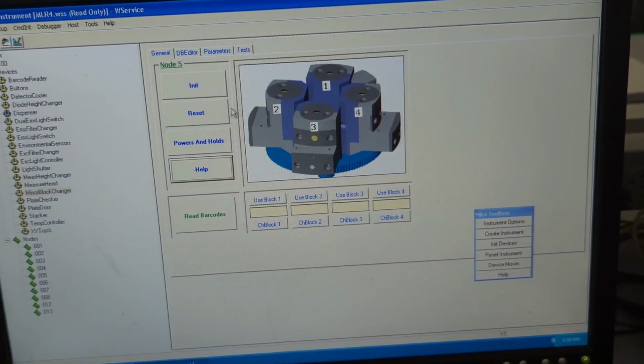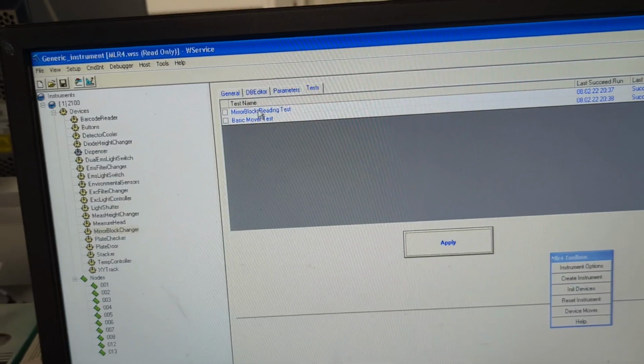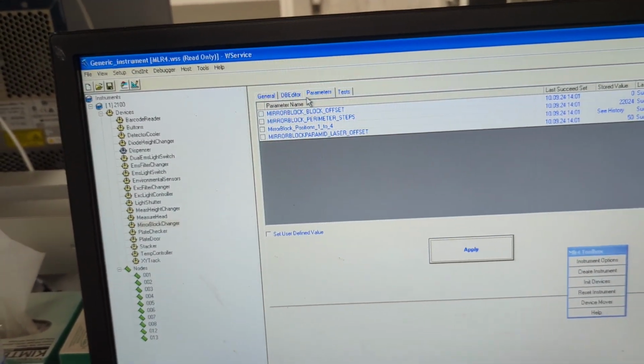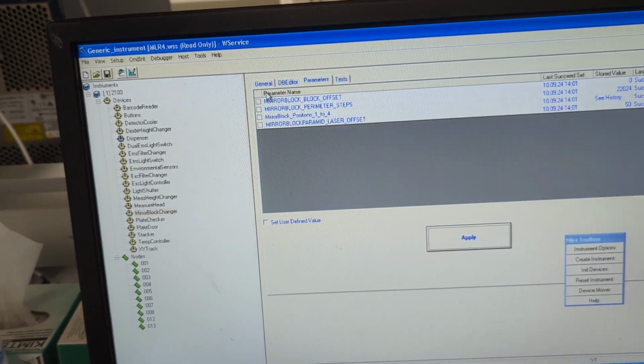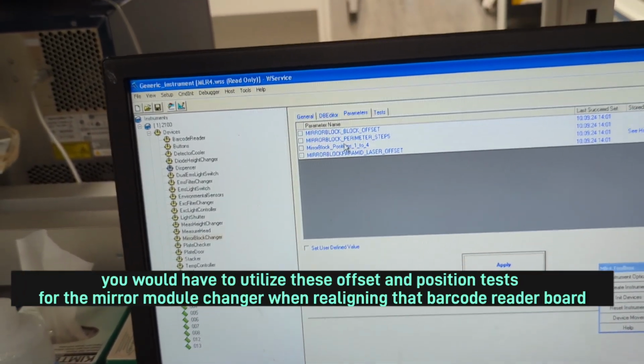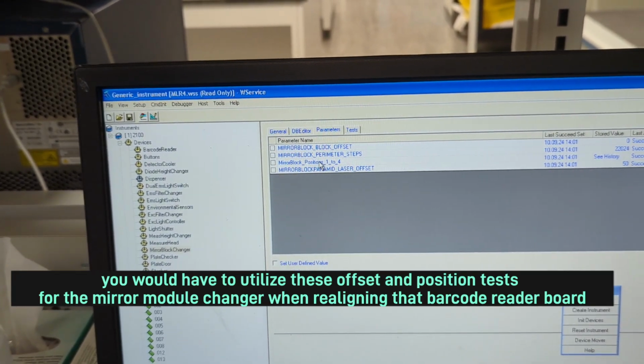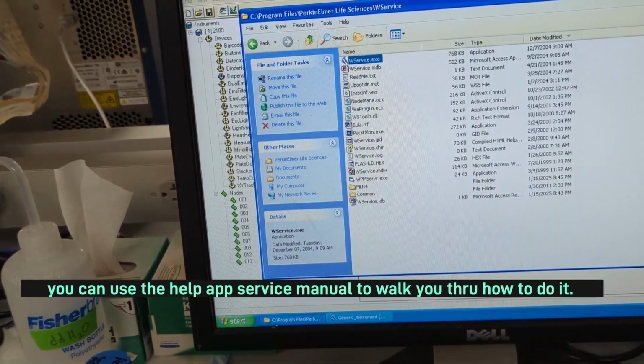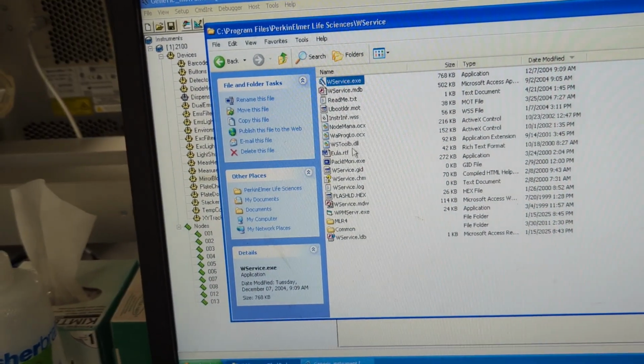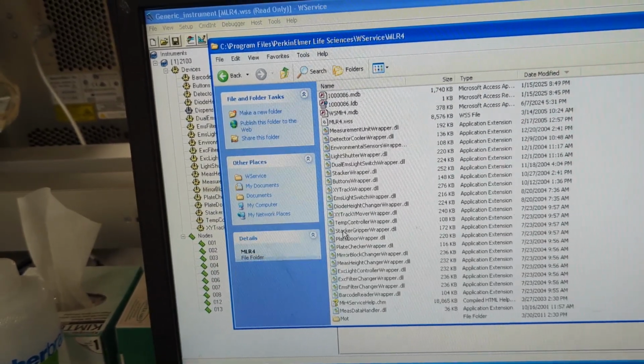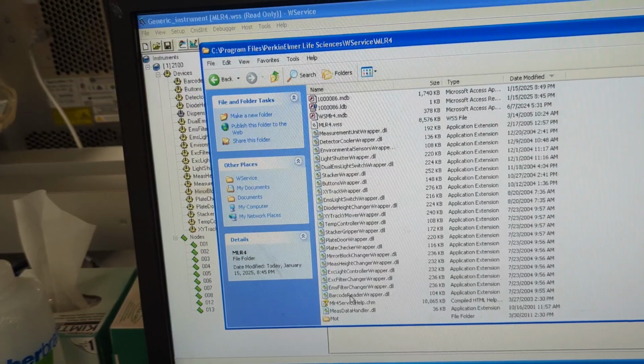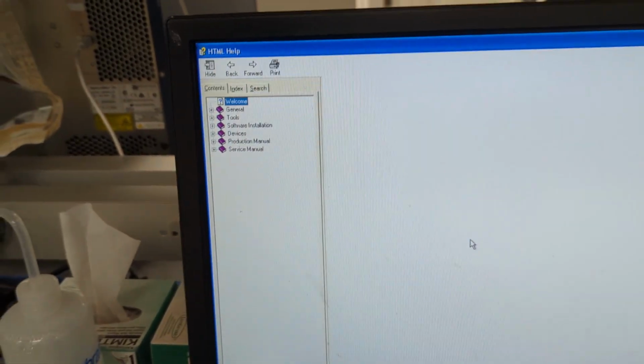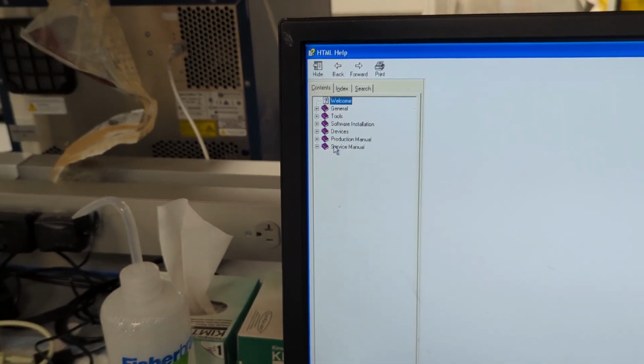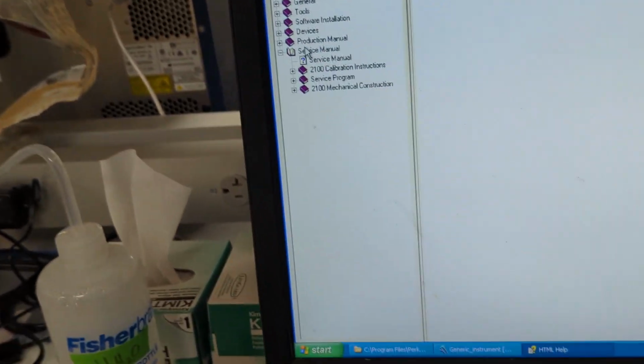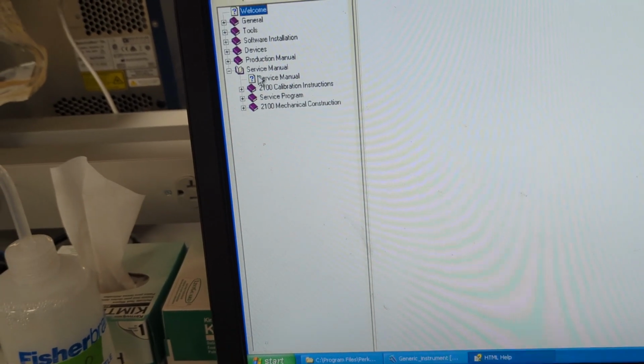you can run it through these tests. For example, for the mirror block offset test, or positions 1 through 4, you just need a specific mirror module. I forget which one you would need, but to help you out, this is a good resource. If we go to MLR4, this folder here, and go to MLR4 Service Help, and then the service manual, which is not the full service manual for the instrument, we go to calibration instructions.